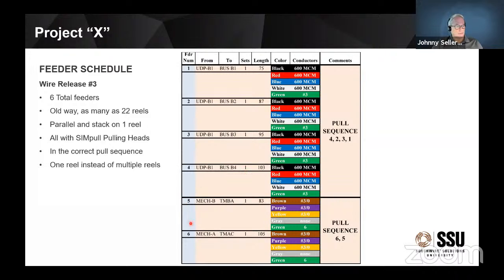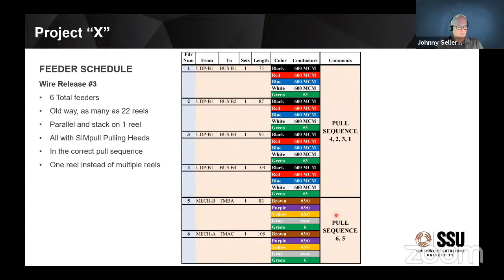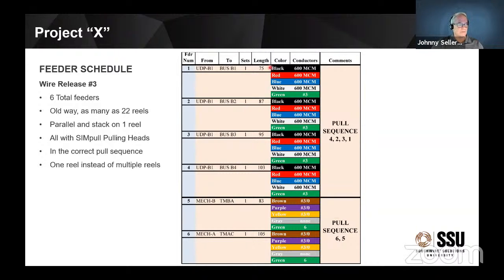The last two feeders are some mechanical feeders originating from two different boards feeding two different loads. So I've got six circuits and instead of 20 or 22 reels, I'm going to parallel and stack them all on one reel, put in the order I want. We're also going to put SIMpull pulling heads on this wire and place pulls in the correct sequence. The contractor says: pull circuit number four first, circuit number two next, circuit number three after that, and circuit number one last. The pull sequence is very important — for example, in a piece of switchgear you want to pull the back conduits first, otherwise you block yourself.